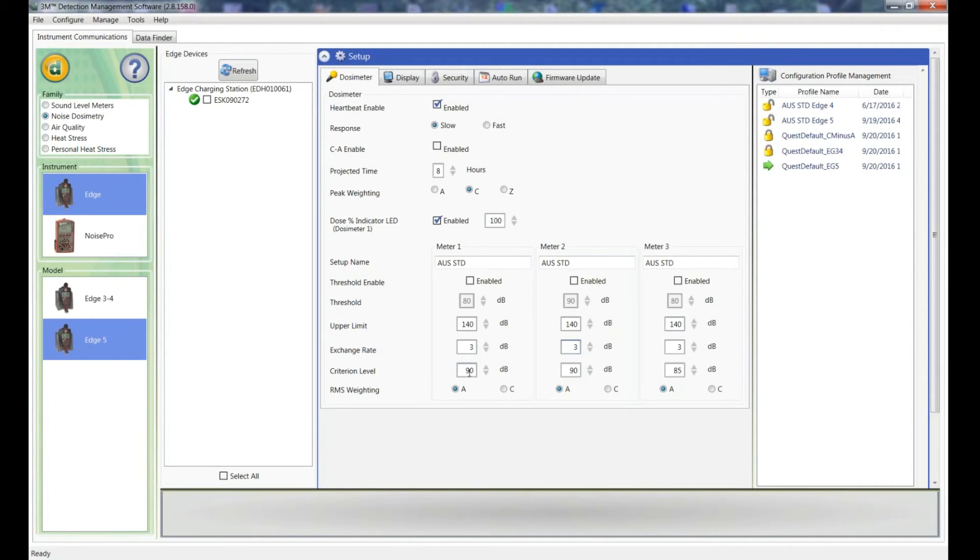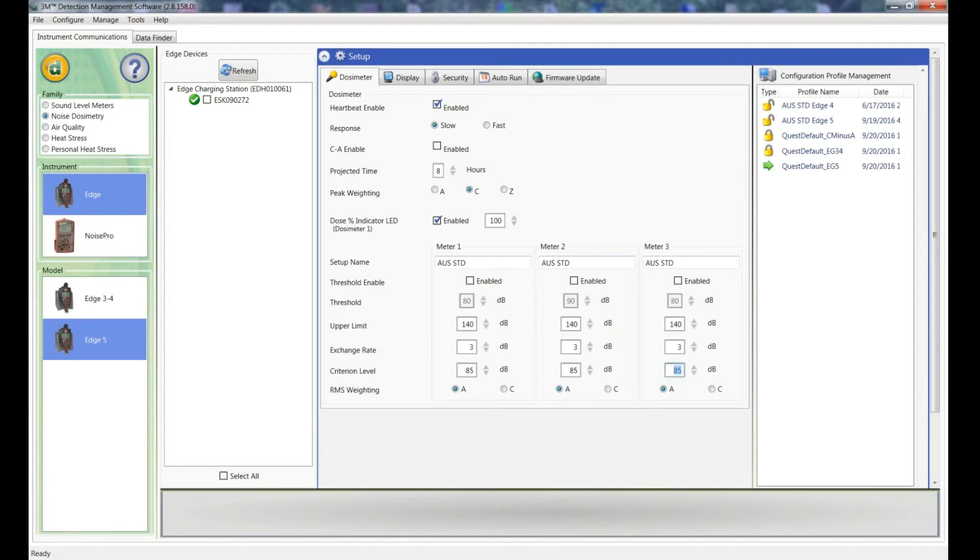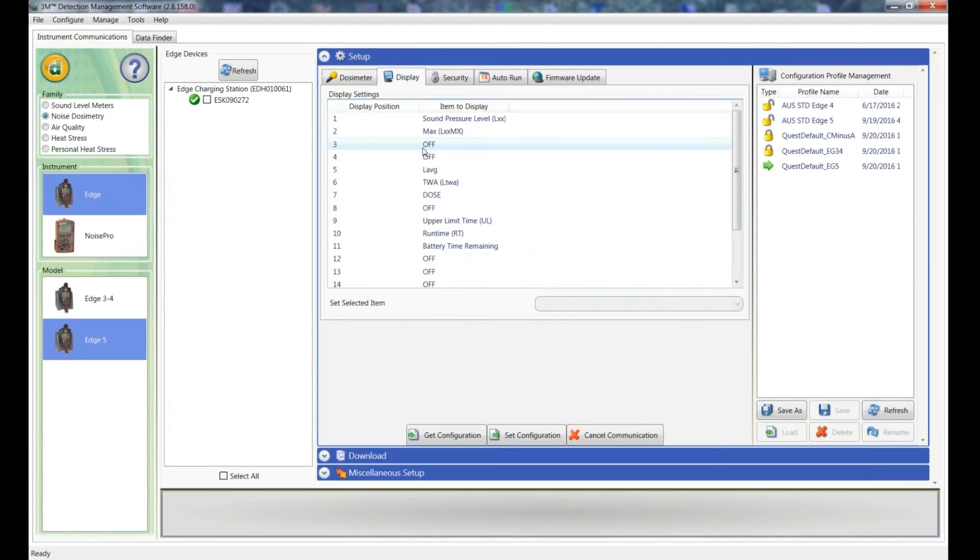And the criterion level which is set out in the standards for Australia is 85 decibels. So that's the LEQ that shouldn't be exceeded for the day. And the weighting we use for the calculation is A-weighted. So that's the dosimeter setup done.